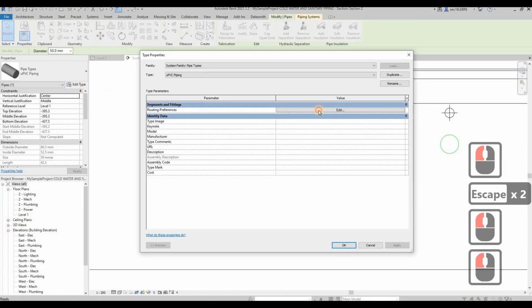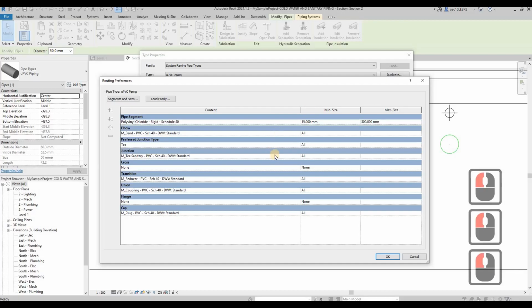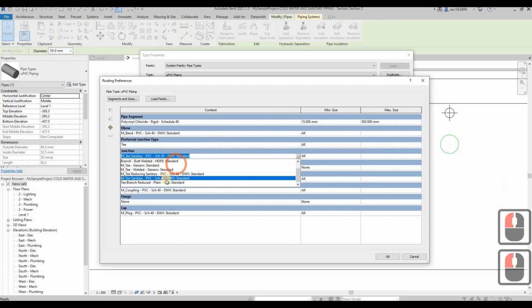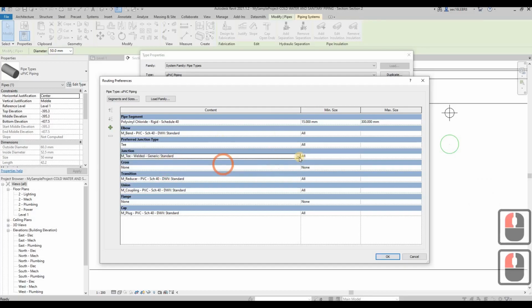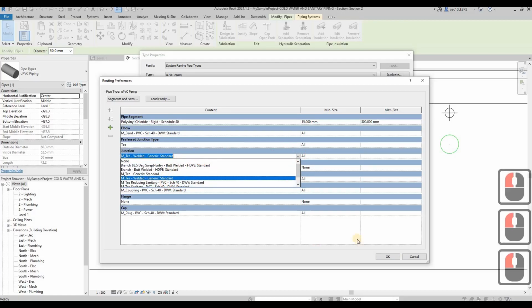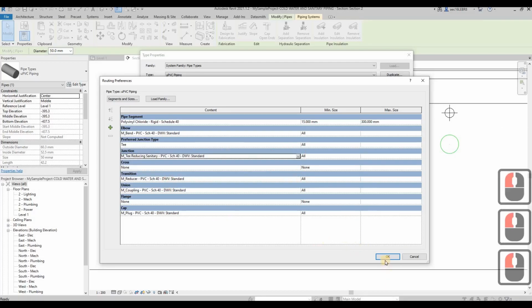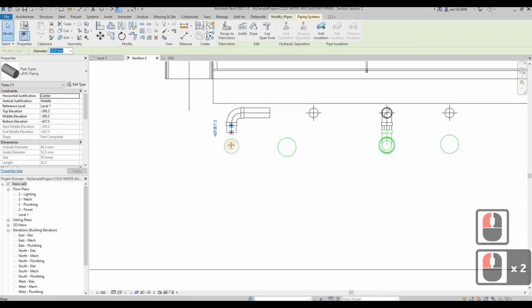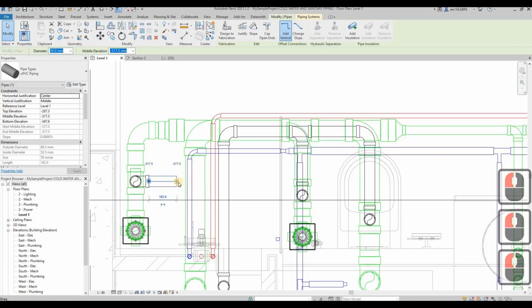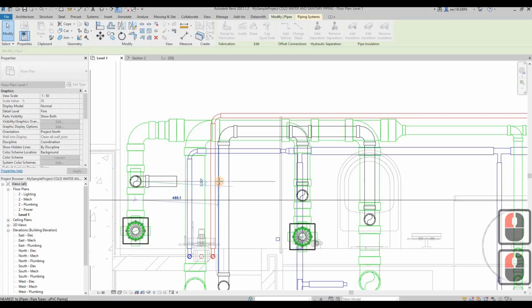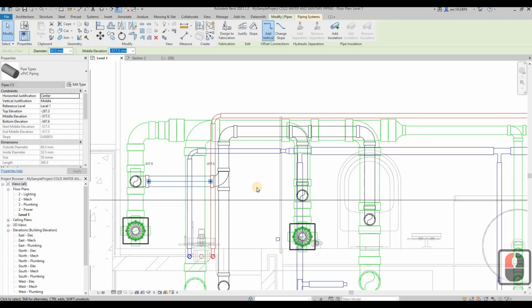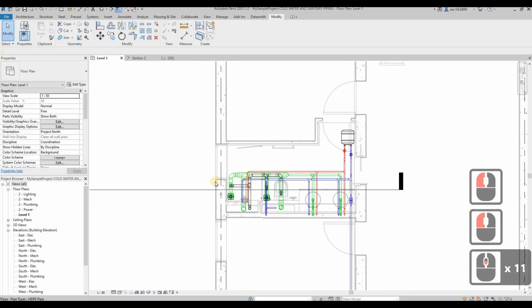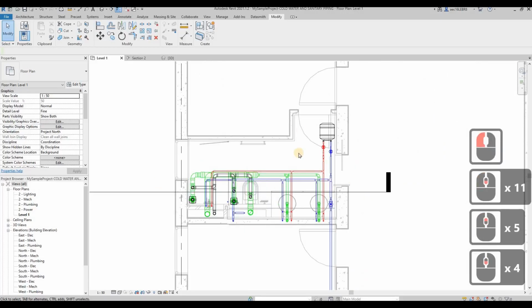Okay, always make sure that you're using reducing T. This one, we use reducing sanitary T. Then just draw. Now the reducing T is formed. Then you connect back your vent pipe to here, to the main. That's how we complete the remaining piping here.